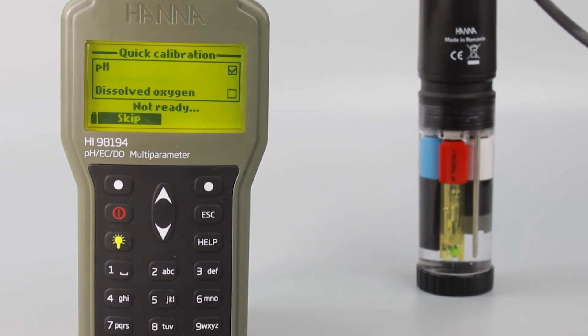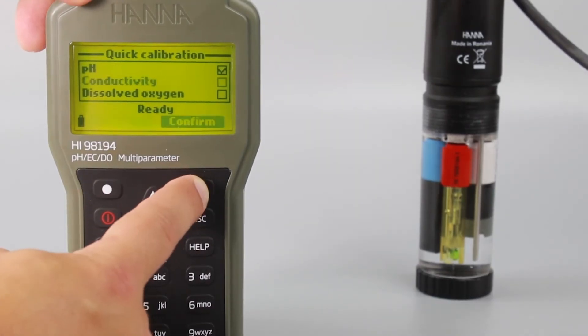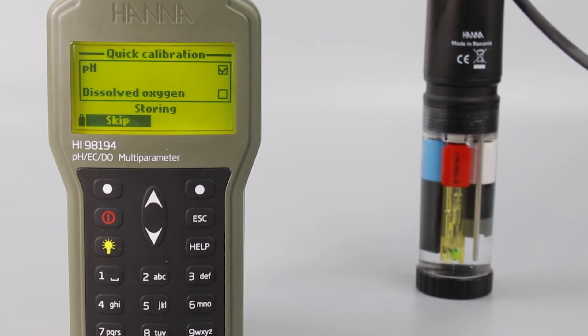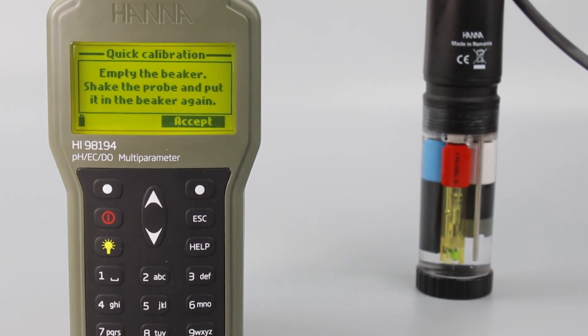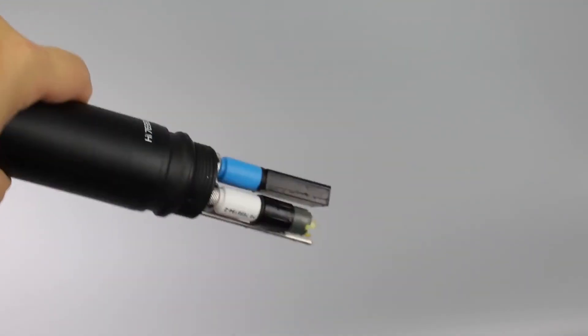Once you get to the dissolved oxygen calibration, you'll be prompted to empty the beaker. Unscrew the calibration beaker and empty the solution. Then, shake any remaining liquid off the probe.